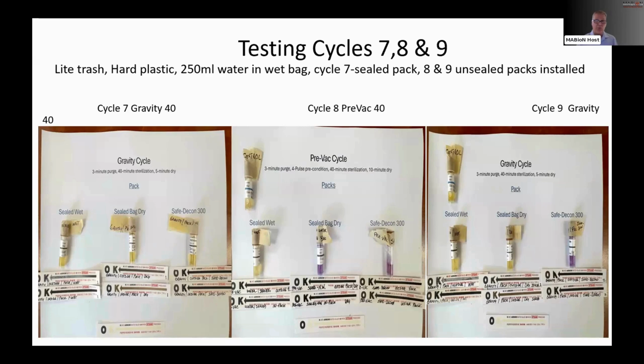And this was a gravity 40. You can see that everything was kind of light. The bags burst. The dry bag burst. The wet sealed one didn't. And you can see some color changes in your strips. On the Safe-Decon, we got really good steam penetration.